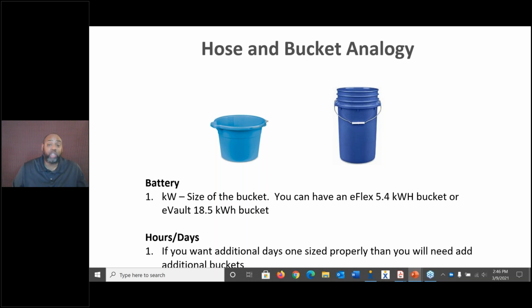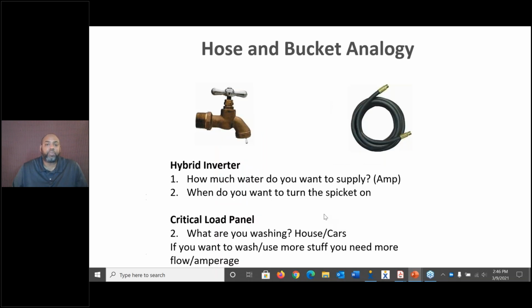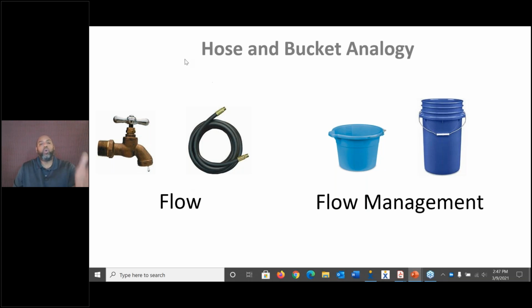Well, what determines how much water is going into these buckets? The hybrid inverter. How many buckets, or how many days of storage I need, that's the hours and the days, excuse me. So if you want additional days, you would need to size your system to account for more days. Just to back up, think of this as flow, hose, bucket, flow management. The inverter determines the flow, the inverter determines the critical load amps. So if someone had a home and they wanted 100 amps of critical load backup, that is all determined by the hybrid inverter. What am I going to do with that ampacity, with that flow, how I'm going to store it? That's when the battery storage comes into play.